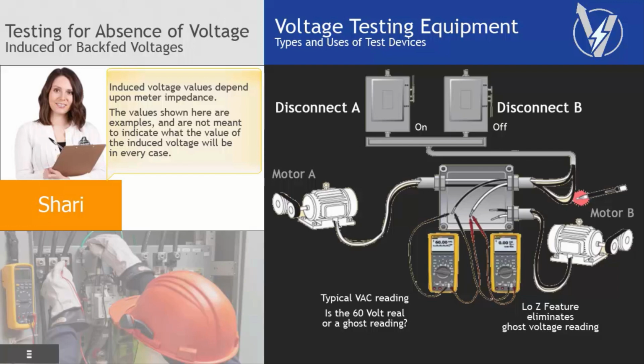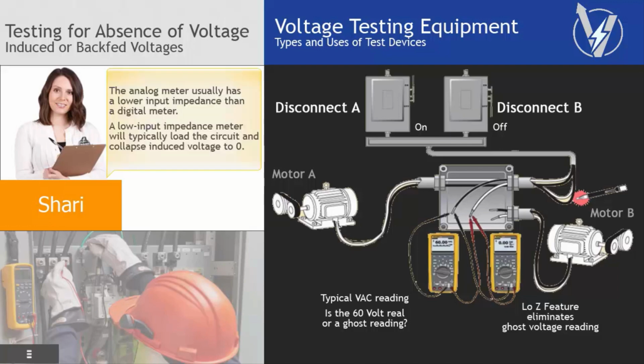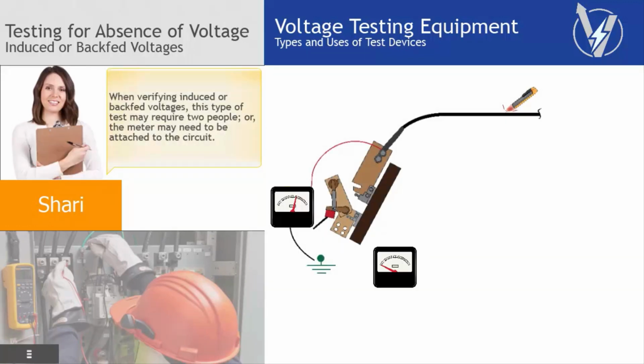Induced voltage values depend upon meter impedance. The values shown here are examples and are not meant to indicate what the value of the induced voltage will be in every case. An analog meter usually has a lower input impedance than a digital meter. A low input impedance meter will typically load the circuit and collapse induced voltage to 0. When verifying induced or backfed voltages, this type of test may require 2 people, or the meter may need to be attached to the circuit.